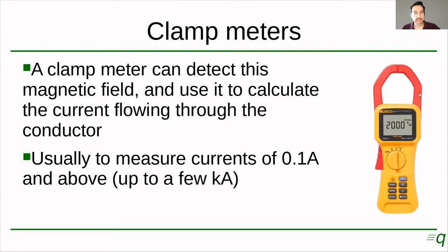A disadvantage is that these things are not very sensitive, so they are usually used to measure very high currents. They can usually measure currents from 0.1 amp or 100 milliamps and above up to a few kiloamps. So this is for big electrical installations really. In electronics their use is limited because of their low sensitivity, but just be aware that these things exist.